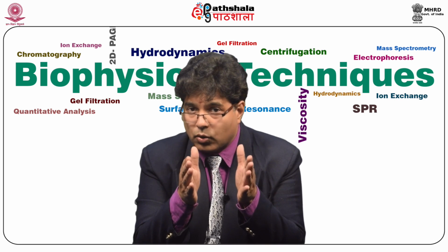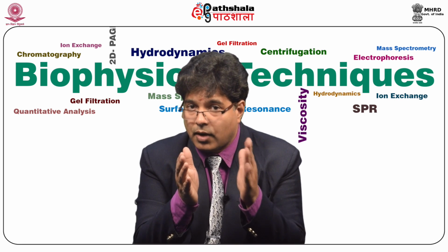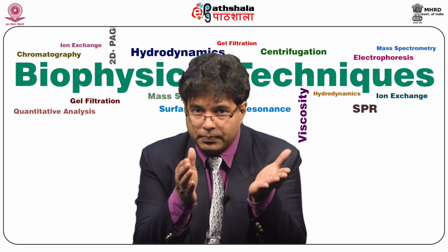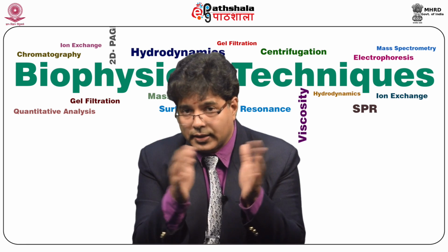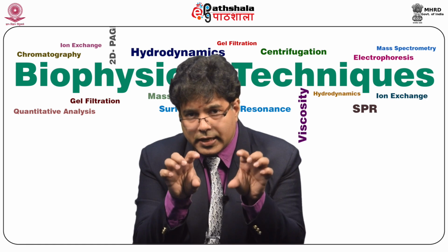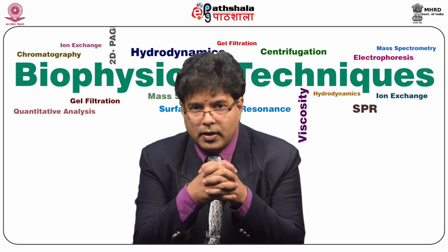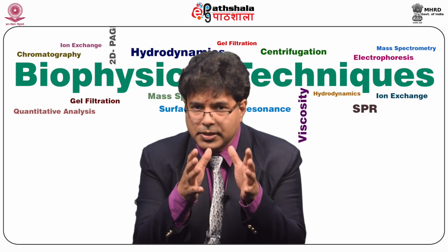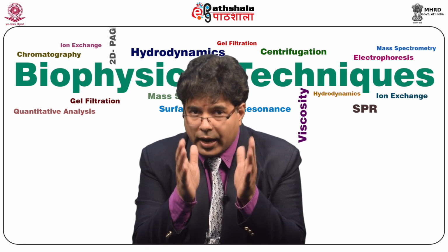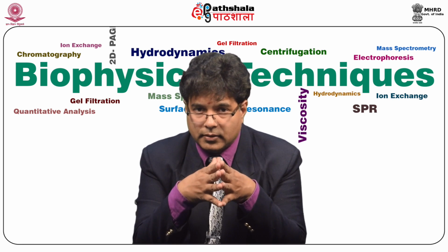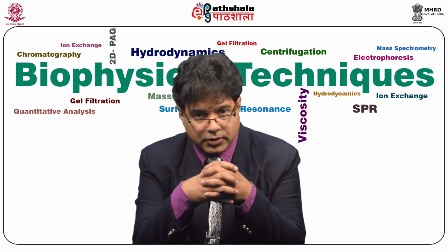Even if two peaks are co-eluting, two analytes are co-eluting, one should not affect the response of the other one. So these aspects we will deal with when we come to do the analysis, and at that time I will explain. But this linear dynamic range of the mass spectrometers is going to determine the accuracy and precision. This is limited by physicochemical processes, chemical preparation, sample preparation steps, ionization, and instrument design, the type of mass analyzer and ion detection scheme which is involved in mass spectrometers.